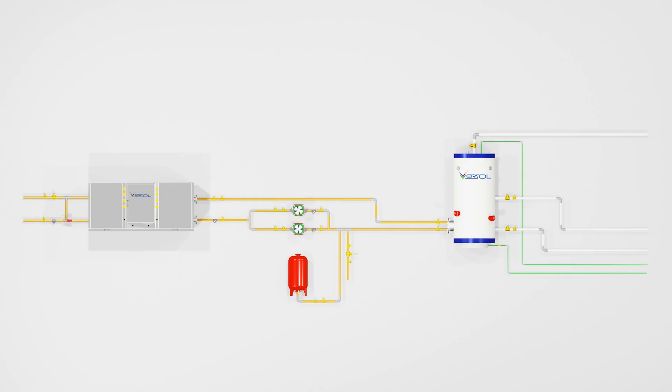During startup while filling water in the calorifier or primary heating circuit, make sure air vent and safety valve are open and cold water inlet pressure is as per requirements. Open cold water line valve. Hot water supply and return valve shall be in closed condition.